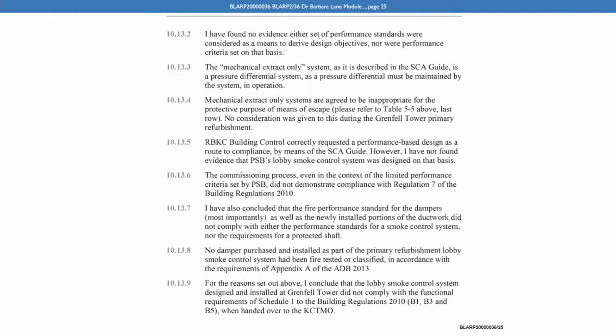She also concludes at 10.13.7 that the fire performance standard for the dampers, most importantly, as well as the newly installed portions of the ductwork, did not comply with either the performance standards for a smoke control system nor the requirements for a protected shaft.